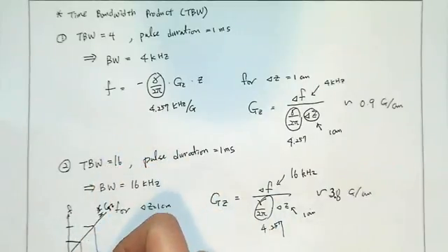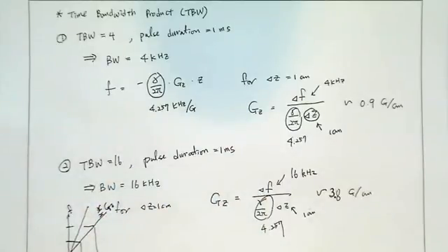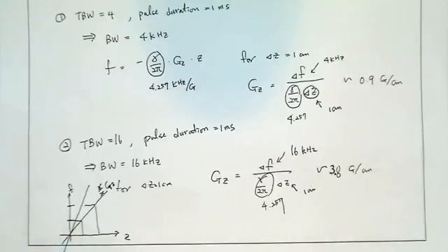So if you want a certain slice thickness, and you're having a bigger RF bandwidth, then you have to have a steeper slope, meaning higher gradient amplitude.